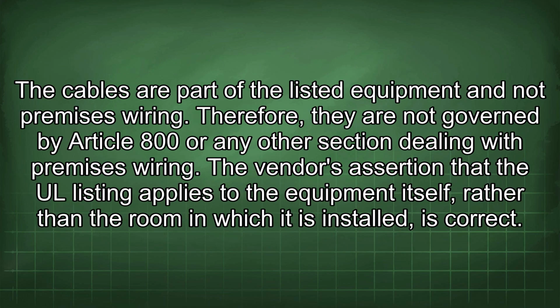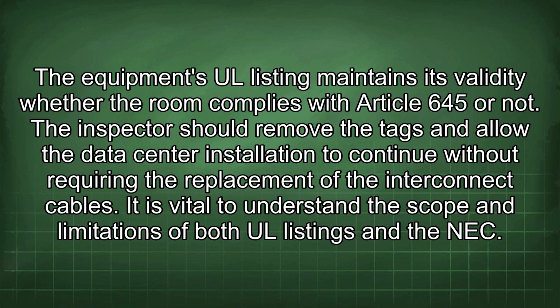The cables are part of the listed equipment and not premises wiring. Therefore, they are not governed by Article 800 or any other section dealing with premises wiring. The vendor's assertion that the UL listing applies to the equipment itself, rather than the room in which it is installed, is correct. The equipment's UL listing maintains its validity whether the room complies with Article 645 or not. The inspector should remove the tags and allow the data center installation to continue without requiring the replacement of the interconnect cables. It is vital to understand the scope and limitations of both UL listings and the NEC.